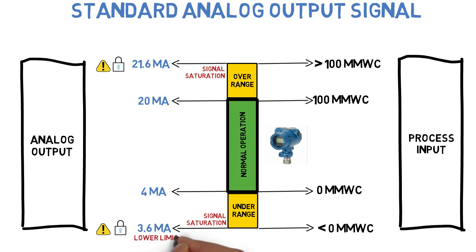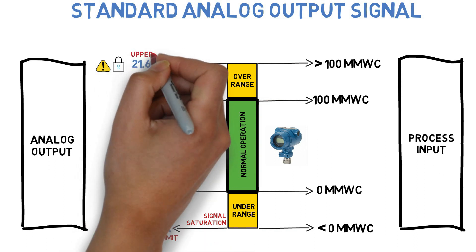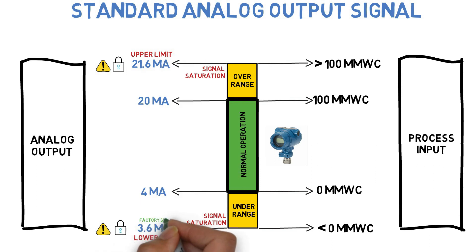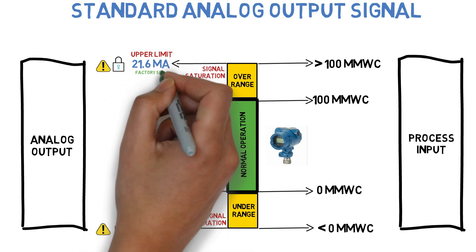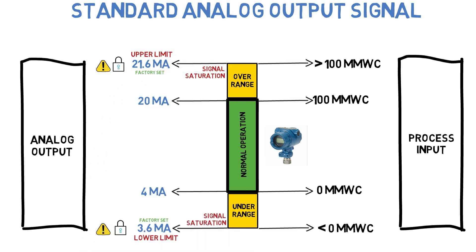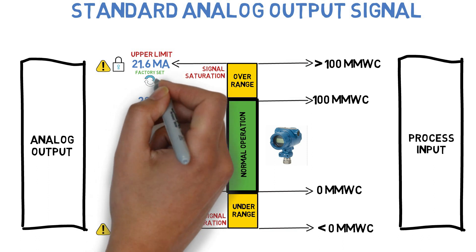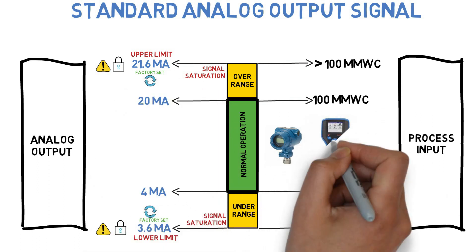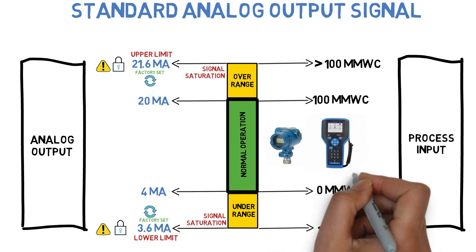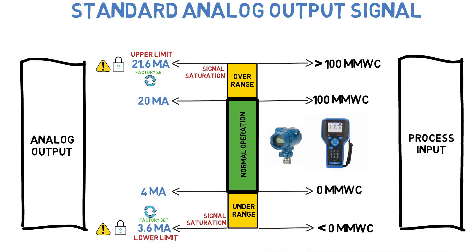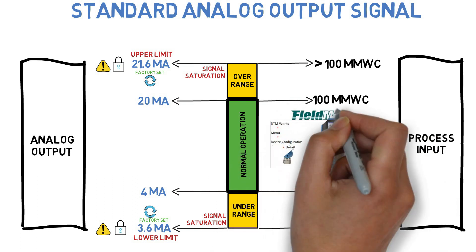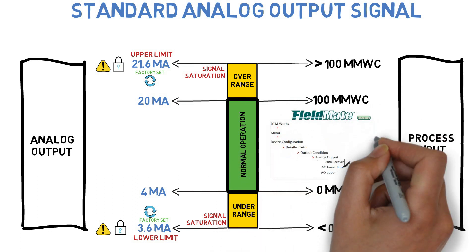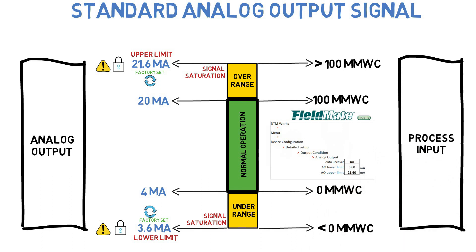The analog output lower limit and upper limit are factory set. These limits are user-selectable within the parameter limits of the transmitter via the HART communicator. This function is available in HART 5 or HART 7.